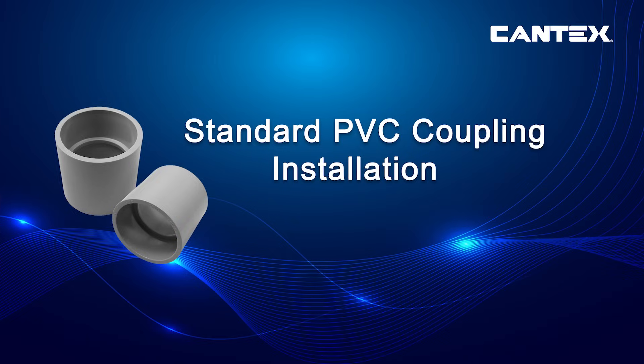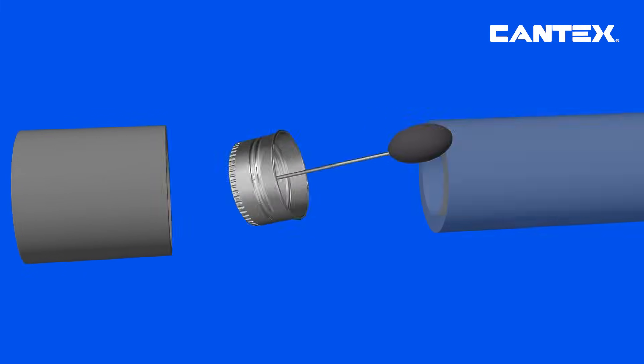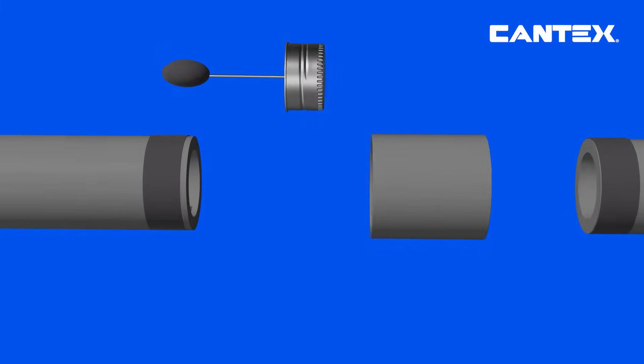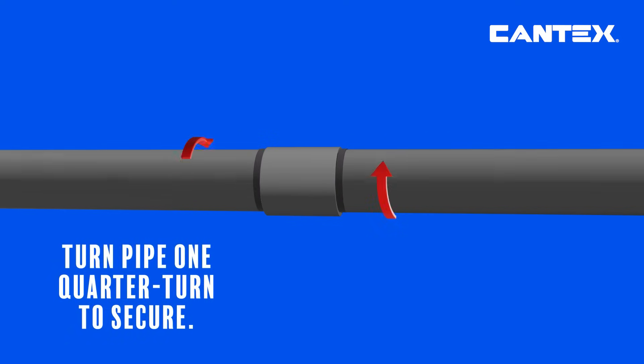PVC couplings are simple to install. Just apply Cantex's PVC cement to the inside of the coupling and the outside of the PVC pipe to be inserted into the coupling. Next, push the conduit ends into the coupling with a quarter-turn twist. Then hold the conduit and coupling in place until firmly fastened.